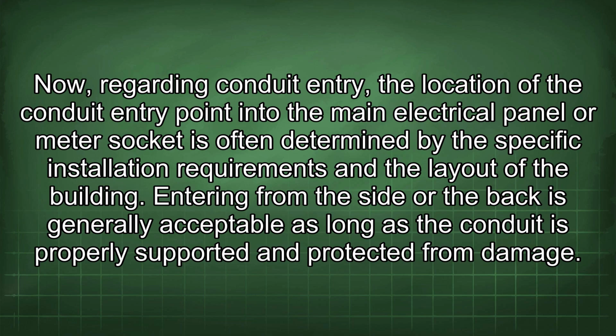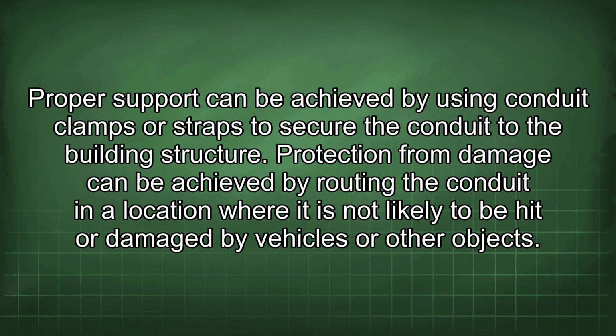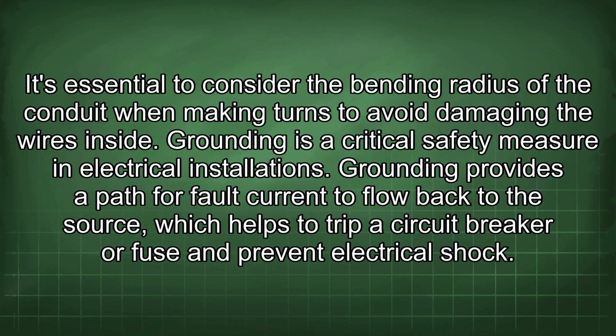Entering from the side or the back is generally acceptable as long as the conduit is properly supported and protected from damage. Proper support can be achieved by using conduit clamps or straps to secure the conduit to the building structure. Protection from damage can be achieved by routing the conduit in a location where it is not likely to be hit or damaged by vehicles or other objects. It's essential to consider the bending radius of the conduit when making turns to avoid damaging the wires inside.